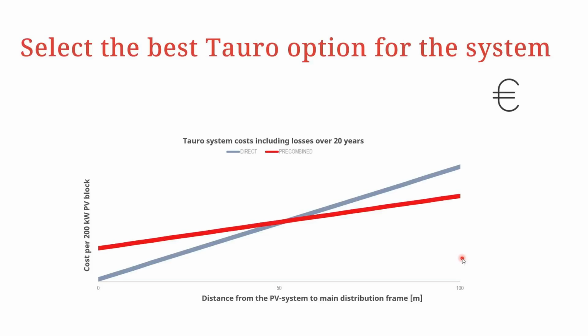So how do we select the best Tauro option for the system we want to design? We've done a simulation, costing the Tauro system over 20 years inclusive of losses, looking at the two options - direct and pre-combined - taking into consideration the cost per 200 kilowatt PV block.